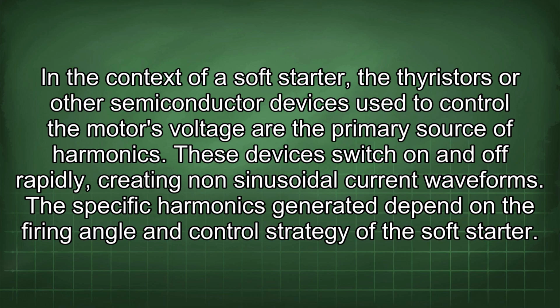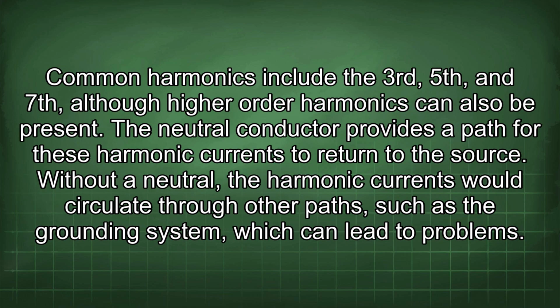In the context of a soft starter, the thyristors or other semiconductor devices used to control the motor's voltage are the primary source of harmonics. These devices switch on and off rapidly, creating non-sinusoidal current waveforms. The specific harmonics generated depend on the firing angle and control strategy of the soft starter. Common harmonics include the third, fifth, and seventh, although higher order harmonics can also be present. The neutral conductor provides a path for these harmonic currents to return to the source.